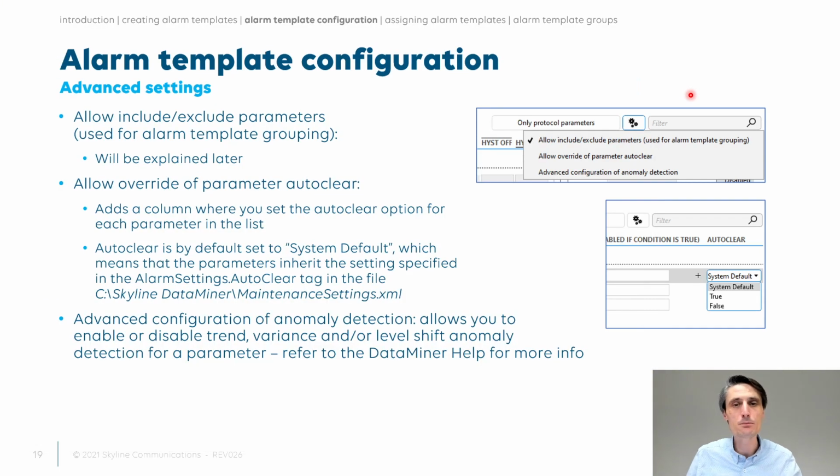So that's the clearable alarms that you can activate. You can activate it system-wide, as I've discussed in the alarm module, but here in an alarm template, you can activate it on a single parameter or maybe a few parameters that are very important that you want somebody to further investigate if ever an alarm happens on it. Even if it's only for one single second that the alarm popped up, it will stay there. So remember that that might come in handy.